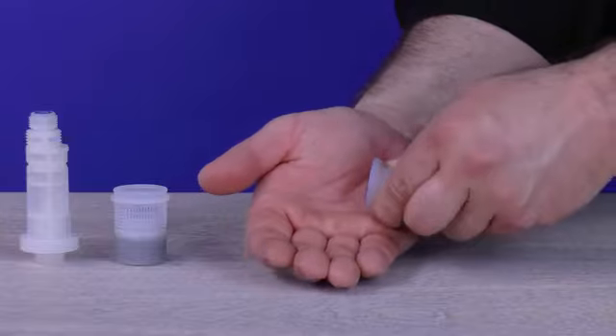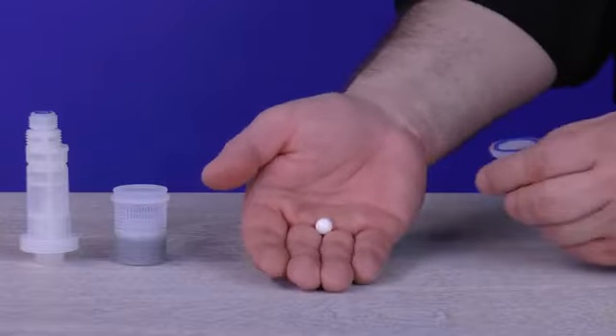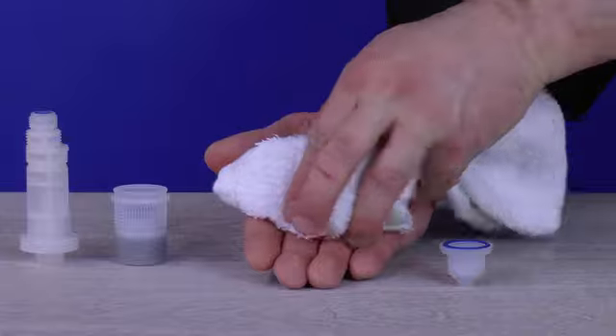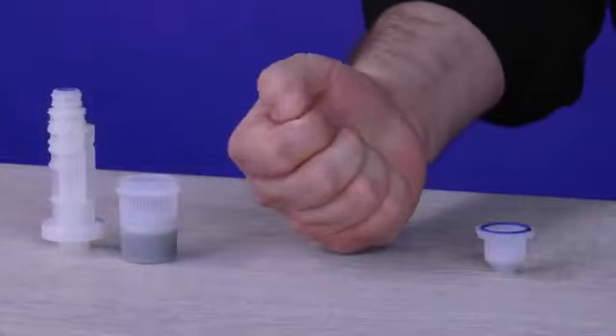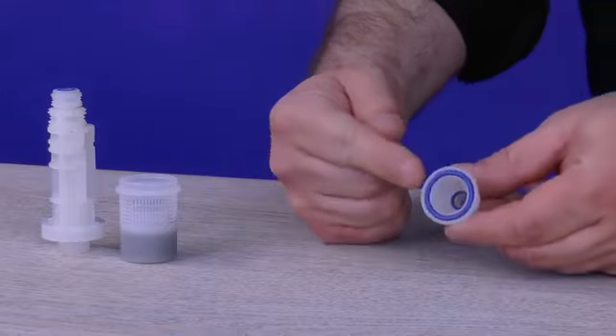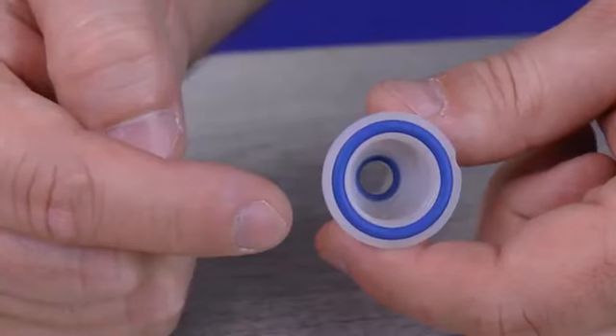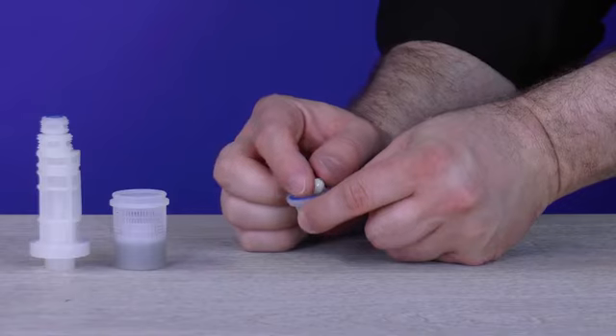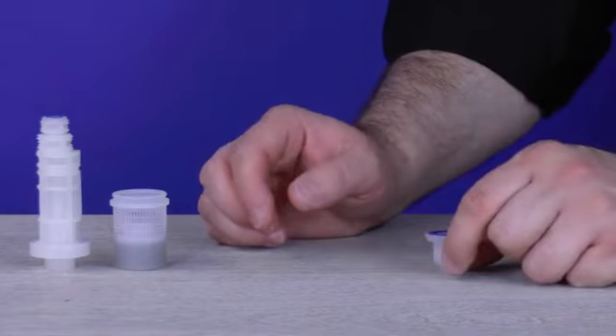Pour the ceramic ball out of the filter seat and into your hand. Set the filter seat down and use a small towel to wipe the ceramic ball clean. Do not misplace it. While holding onto the ceramic ball, inspect the 2 blue O-rings in the grooves of the filter seat and make sure they are not damaged. Put the ceramic ball back into the filter seat and set the filter seat aside.